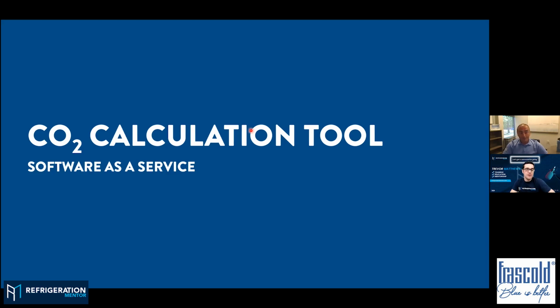Yeah, and that's one of the uniquenesses of CO2 when you start to learn about it: you've got to have a minimum superheat, but you also want to keep your discharge temperature down. So it's a happy medium, especially for designers out there. It's something you need to take special care looking at, whereas for standard refrigerants, HFCs, HFOs, you didn't have to look at that as much. I guess the HFOs run a lot hotter than the HFC refrigerants, but it's something you've got to be checking every time. It doesn't matter what compressor it is. Yeah, correct. Or whatever refrigerant it is, I guess.